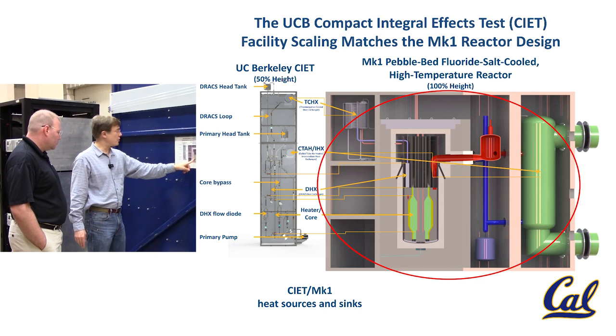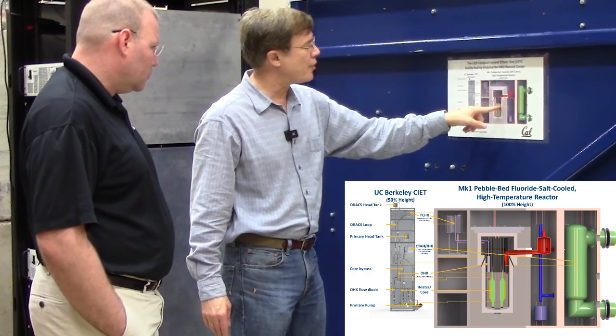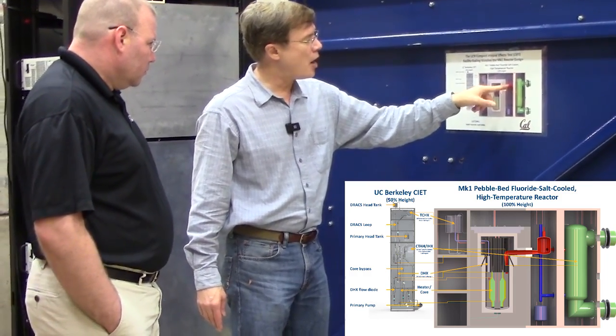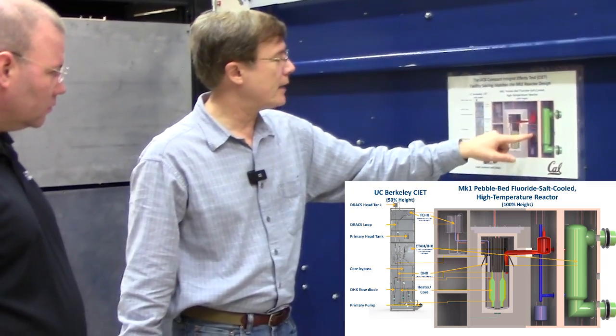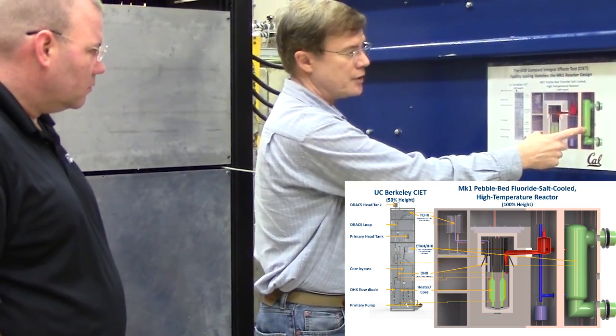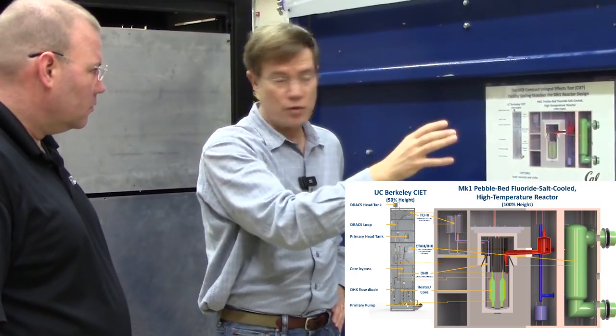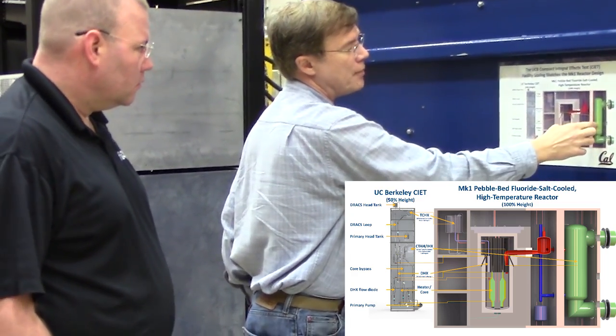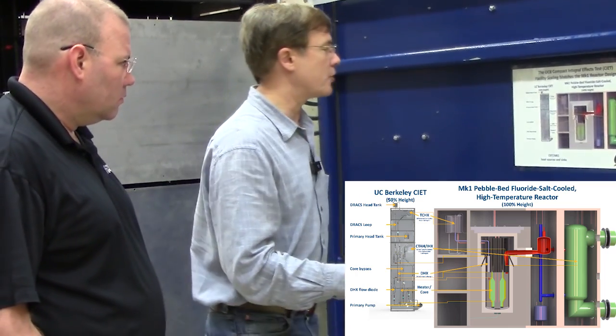This is a pebble bed, fluoride-salt-cooled pebble bed reactor — the Mark I PB-FHR design. Here's the annular pebble bed core. Coolant flows in through the bottom of the core, up through, out into a hot well, and then from the hot well it is pumped by cantilevered, overhung centrifugal pumps through the air heater and then back up into the reactor. There are two coiled tube air heaters and air ducts that bring air from a GE Frame 7 gas turbine modified for external heating. The air flows up through the tube bundle and back to the turbines, heating the air to 670°C for expansion in the turbine.